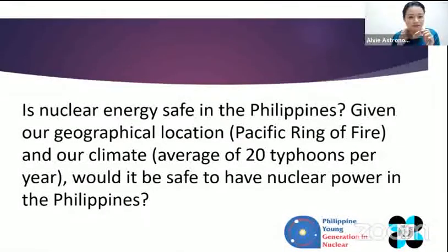To support Dr. Arcilia's answer, even before a construction permit can be issued to a nuclear facility, a very extensive siting study has to be conducted. Dr. Arcilia knows the details of this. That includes not just the seismic characterization, but also the geotechnical hazard, the orography of the location, and so on, and all of those are considered in designing the plant. So in the site study, the consultants should know the maximum possible earthquakes that could happen in that location, whichever.